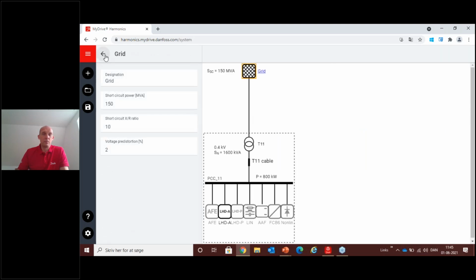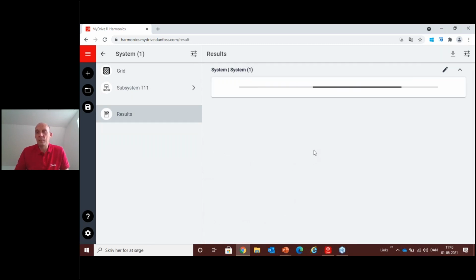So 4 of those instead. Then I'll go to the results and recalculate. Now I'm calculating what it would be like if I chose to use low harmonic drives instead of standard drives. What would be the outcome? It just calculates for a bit, so we need a little patience here. It normally doesn't take that long.